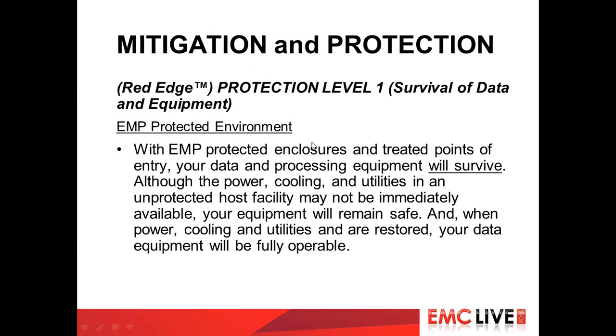What we tend to look at, at ETS Lindgren, is two levels of protection. Protection level 1, as we call it, is survival of data and equipment—protecting the critical equipment with a shielded environment, with all points of entry addressed. In this scenario, the data center itself might go down during an event; the power systems and cooling systems might be lost, but all of the equipment located within the protected EMP environment would be safe and able to be restarted once the utilities and cooling are restored.